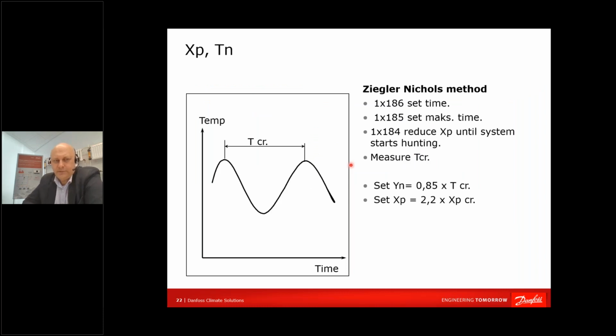Okay, how to tune a PI controller? You might use the Ziegler-Nichols method. When you are setting the integration time of your actuator, of your system, you change TN to the maximum value. Then you reduce XP until the system starts hunting back and forth. You measure the critical time, and you enter these settings into ECL, just multiplying the values which resulted in the oscillation.